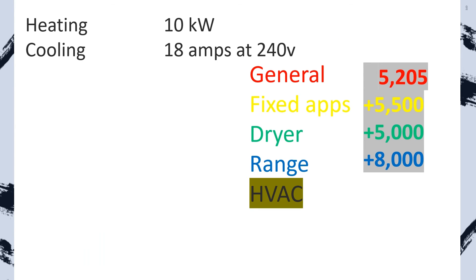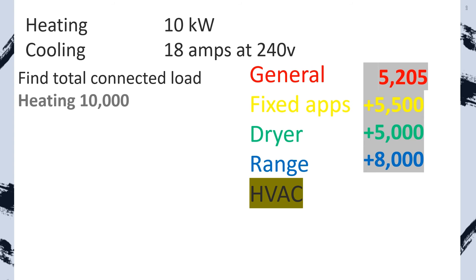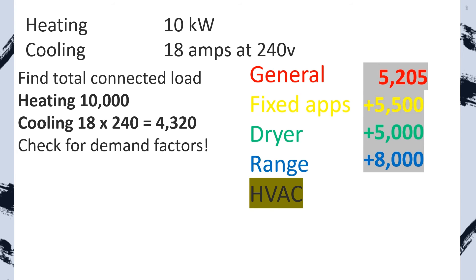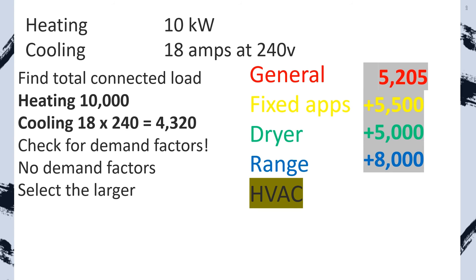Now for our HVAC VAs. We're going to take the larger of the heating or cooling. First, find our total connected load: our heating is 10,000, and our cooling is our amps multiplied by our volts, which equals 4,320. Now we check for demand factors — there are no demand factors on this portion, so we're just going to select the larger of the two, and we put down 10,000.